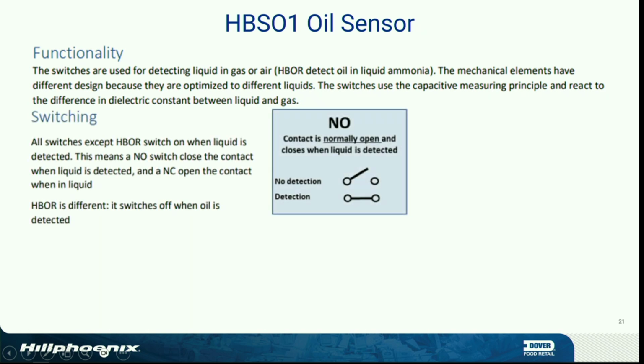And as I said, they have two types of switches, normally open, normally closed. We do have normally closed switches that will open. All right, we'll use them usually on liquid detection, like a receiver or a suction accumulator. All switches except HBOR switches switch on when liquid is detected. This means an NO switch closes the contact when the liquid is detected, and an NC opens the contact when the liquid is detected.